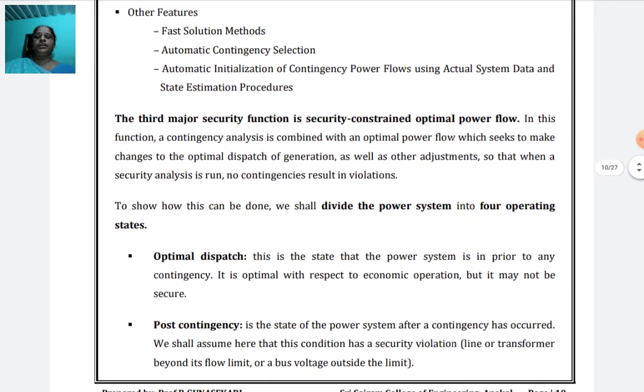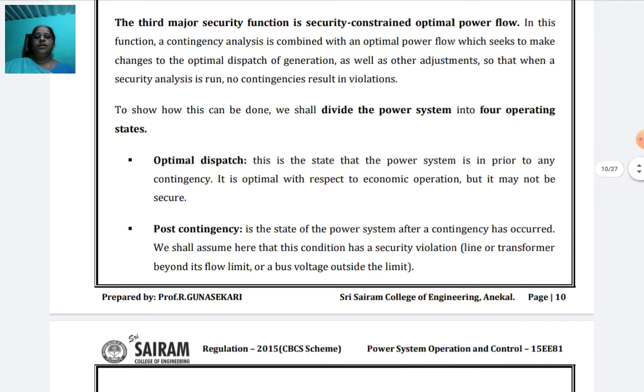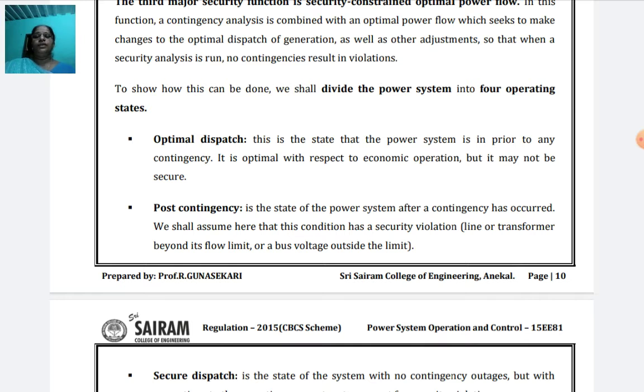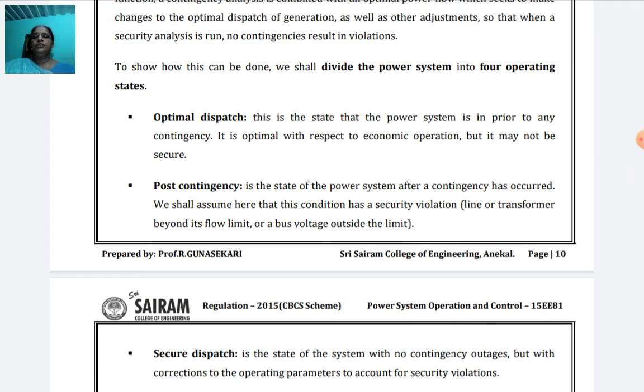Then the third major security function is security constrained optimal power flow. In security constrained optimal power flow, the system is divided into four operating states. First one is optimal dispatch. In optimal dispatch, the power system is not secure against any contingency, but it is optimal with respect to economic operation, though it may not be secure. Second one is post contingency. Post contingency is also one of the states of the power system. After a contingency occurs and the problem has occurred, the line flow limit or the bus voltage limit exceeds the reference limit. Therefore this is the post contingency state.